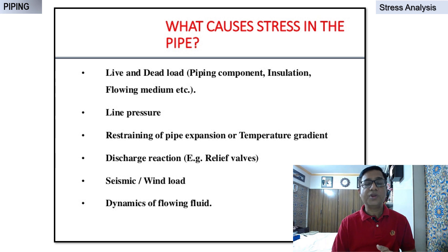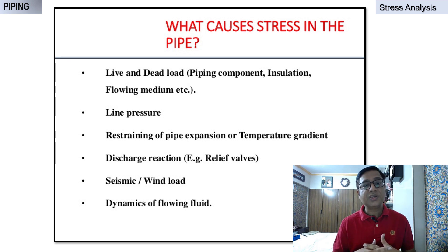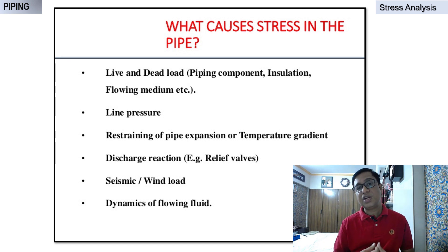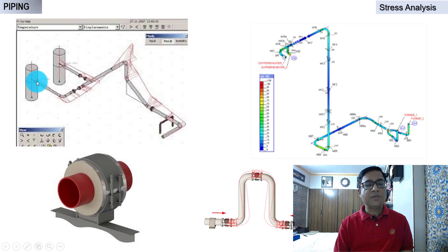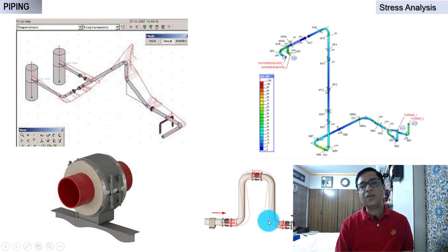What causes stress in pipes? One is the live load — the load of the piping itself — then line pressure from the fluid flowing at certain pressure, restraining of pipe expansion and thermal gradient, discharge reaction, seismic loads depending on the zone, wind loads, and dynamics of the fluid. You can see how the stress is shown in the analysis — there are various stress ranges. Pipes anchored at both ends will have stress like shown. The stress analysis output determines what kind of supports are required.